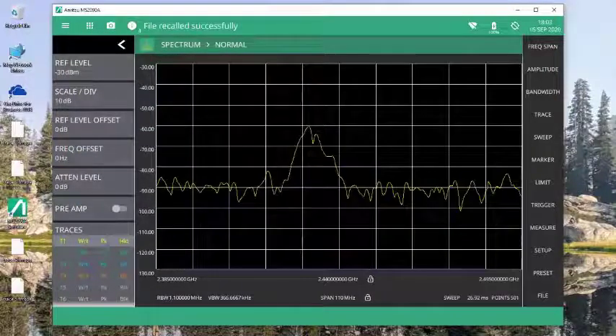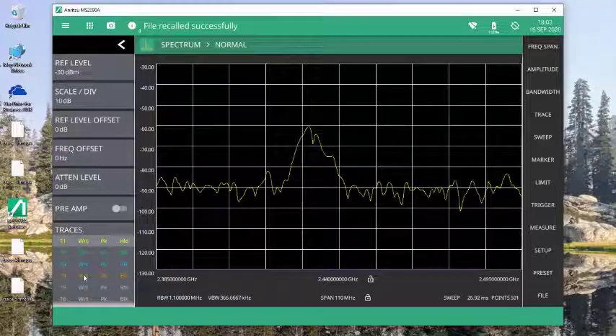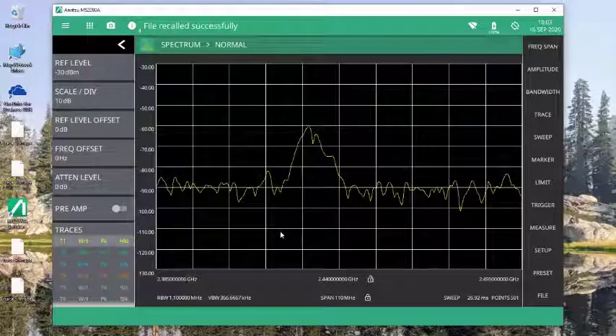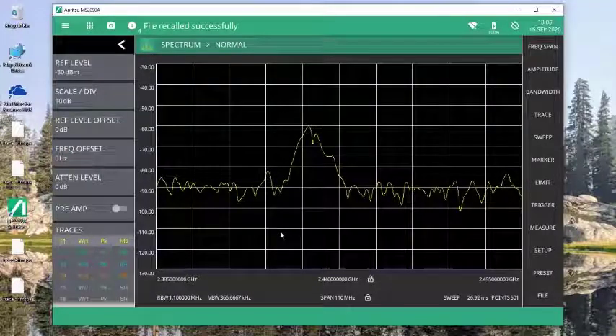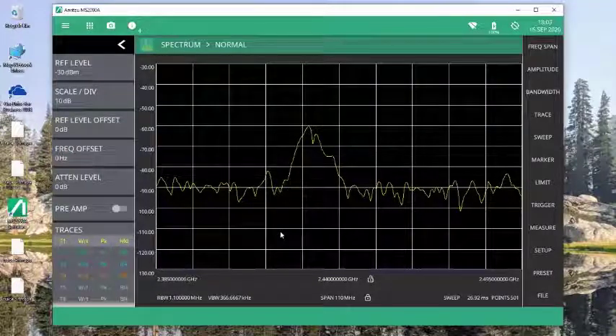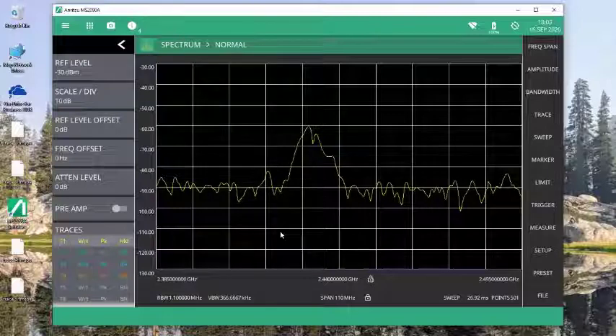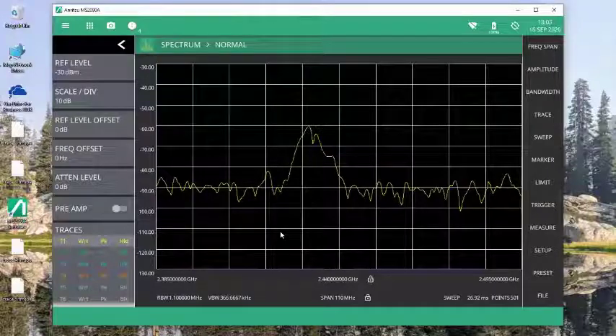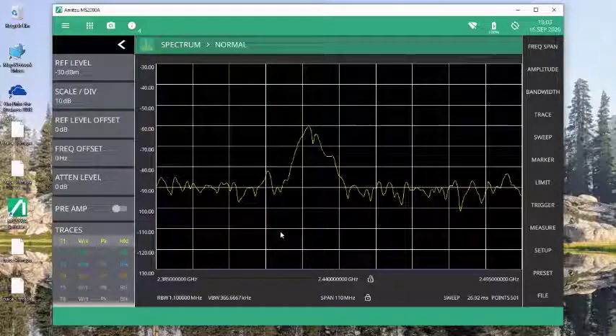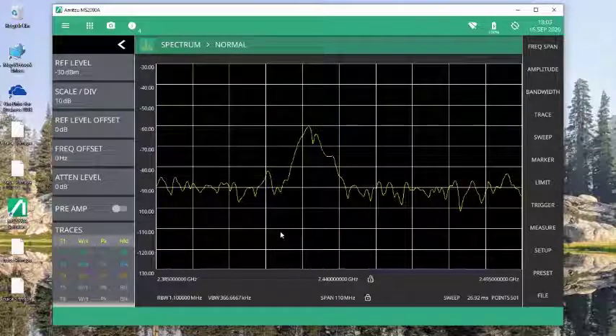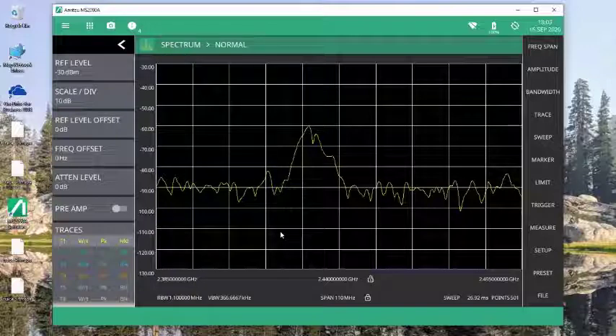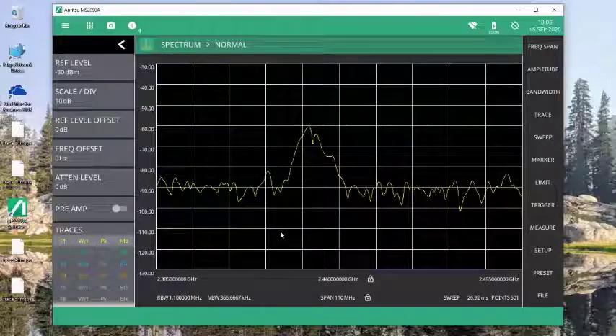the trace 3 disappears. That's because as I'm recalling the trace data, I'm also recalling the setup with which the trace data was saved. So I need to go back and turn on that second trace and set it back to sweeping.